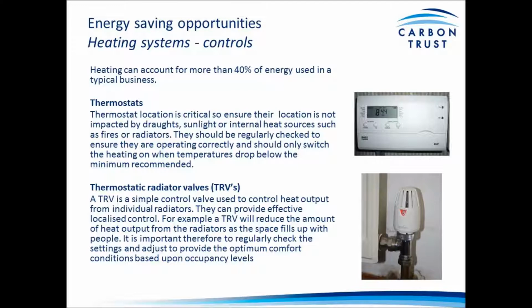You should really be thinking about where your thermostats are located. If they are near drafts or external openings, in direct sunlight, or near internal heat sources such as printers or process machinery, then they will not be reporting accurately on ambient conditions. The image shown here is a boiler controller with built-in thermostat, but this logic applies to thermostat control of all kinds for heating and AC systems. A common one we often see for fan heaters in warehouses is locating thermostatic controllers near large roller shutter doors, which can clearly hamper the recording of internal temperatures if it's just recording the external conditions when the door is open.